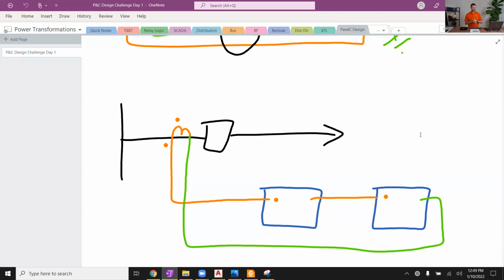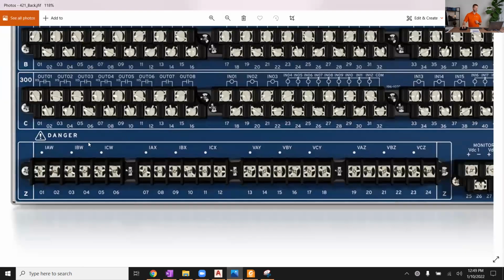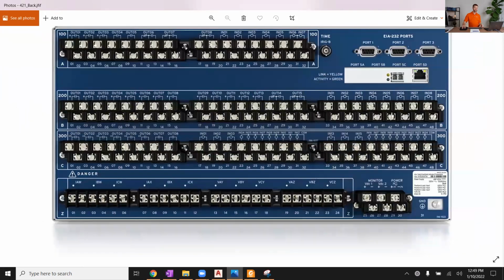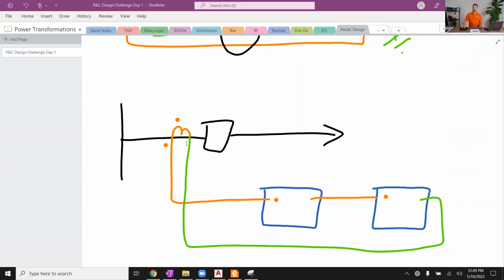Let's stay focused on CTs for now, PTs on our analogs. So we're looking at the back side of the relay things. That's what we've been kind of diving into here. But next I want to take you to the other end of things. What about on the CT terminals themselves? You know, we looked at these current terminals on the back of our relay. But where are these CTs coming from?